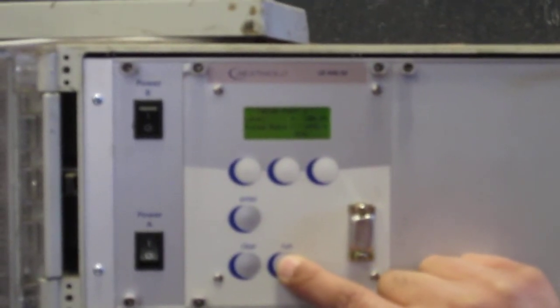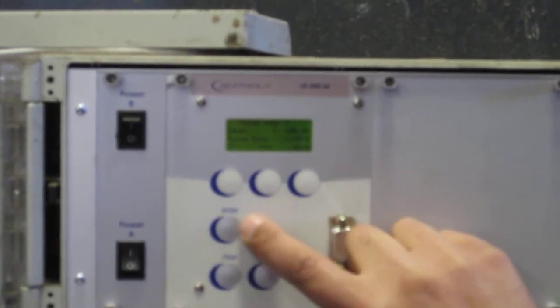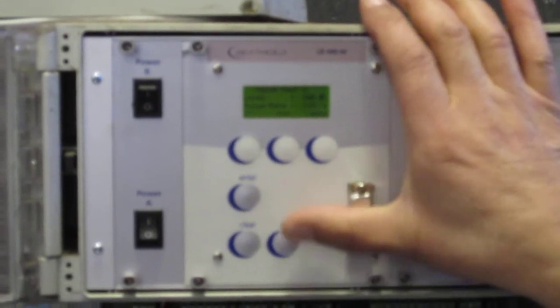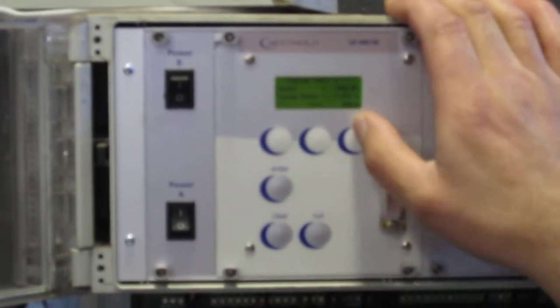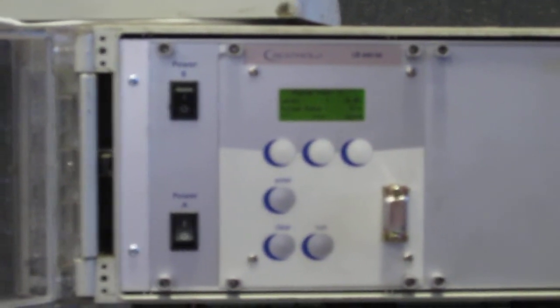We waited 4 minutes, and then we say take it out of run. It's settled down. I don't see nothing but this last number moving. We say enter, and we say enter. So we take it out of run, then push enter, and so now we've got it calibrated. It's my value pair 2. Now, assuming we've already did value pair 0 with the source open, we skipped over that.